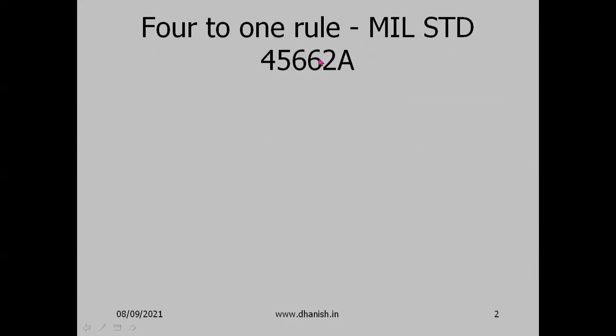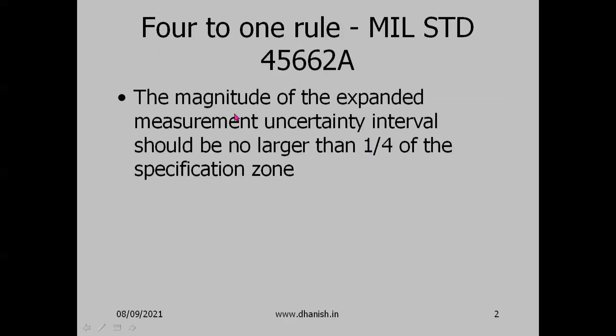One of the first rules to discuss the issue of measurement uncertainty was the MIL standard — military standard 45662A of the United States, developed during the Second World War. The rule states that the magnitude of the expanded measurement uncertainty should be no larger than one-fourth of the specification zone, which is the allowed limits as per the designer. The specification zone is defined by the upper specification limit (USL) and lower specification limit (LSL).